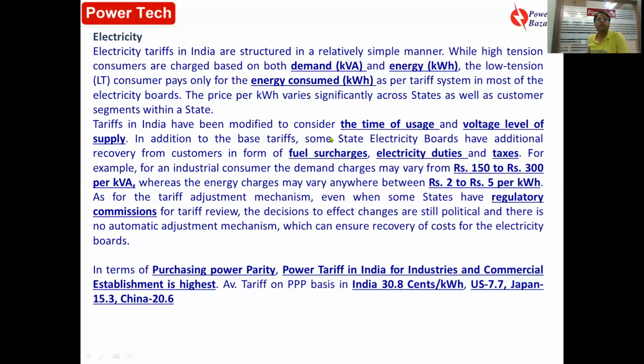Tariff is also decided based on voltage level: LT voltage, HT voltage, or EHT voltage. 132 kV and 220 kV are extra high tension (EHT) voltage; 11 kV and 33 kV are HT voltage; and 400 volt, 230 volt are LT voltage or low tension voltage. So based on the voltage level of supply, tariff is decided. Apart from that, some distribution companies charge fuel surcharge, electricity duties, and taxes. This is how electricity is charged for an industrial consumer and for an LT consumer.